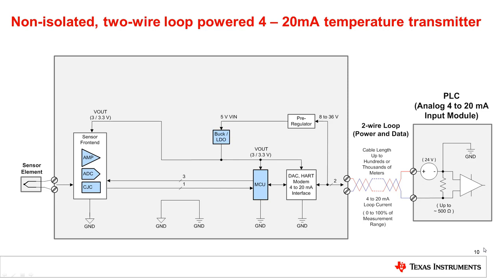In this case, we are talking about a 4 to 20 milliamp system, where we have the transmitter on the left side and the PLC as a receiver of the 4 to 20 milliamp signal on the right side. The transmitter itself consists of a sensor front end, an internal power regulator such as a step-down converter or an LDO, an MCU, and a D-to-A converter and HART modem to complete the 4 to 20 milliamp interface. There may also be a pre-regulator which converts the loop voltage — ranging from about 8 to 36 volt — down to an intermediate voltage of, say, 5 volt.